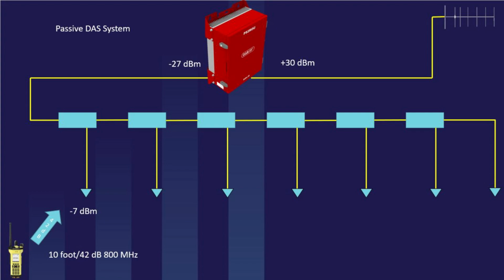Portable running 35 dBm, 10 feet away from an antenna, drives the antenna at -7 dBm and drives the input to the BDA at -27 dBm due to passive losses. It needs 57 dB of gain to get to full power, where the BDA is 30 dBm. The donor antenna gain system would have to be under 7 dB total in order for this to be a legal installation and maintain the ERP as specified in Section 90.219. So that's the pretty simple way to do this.